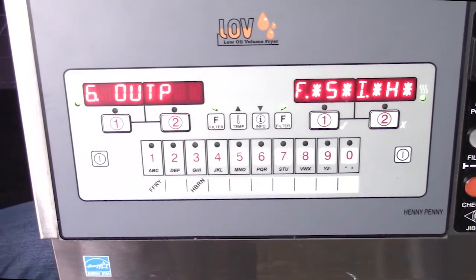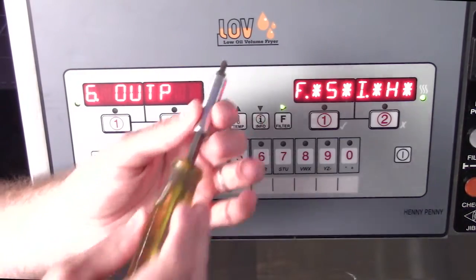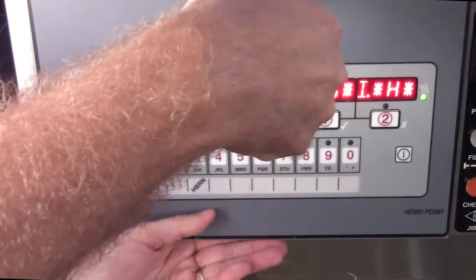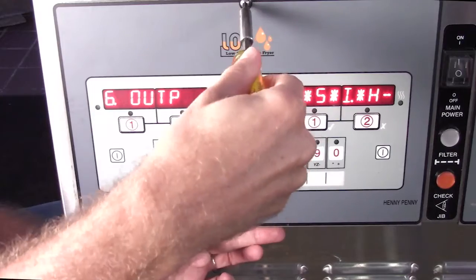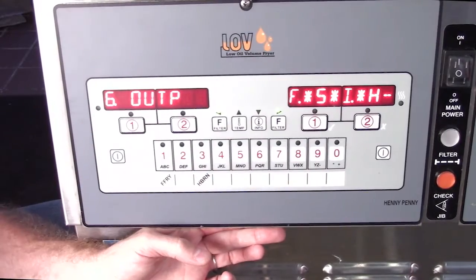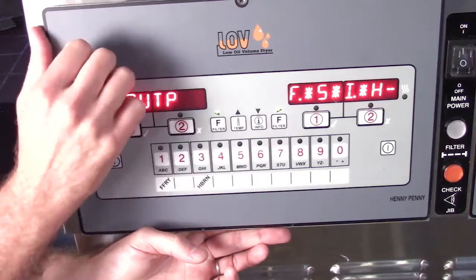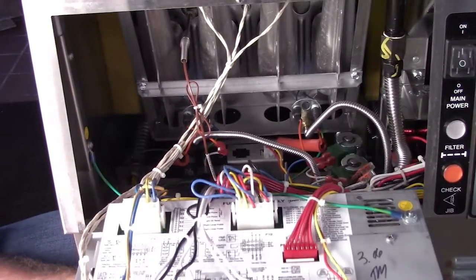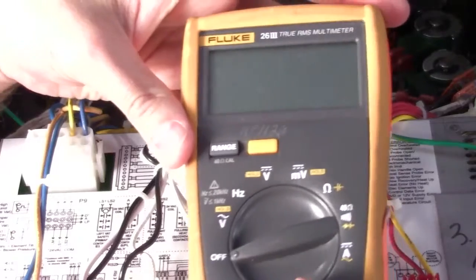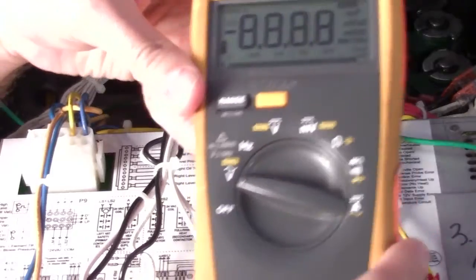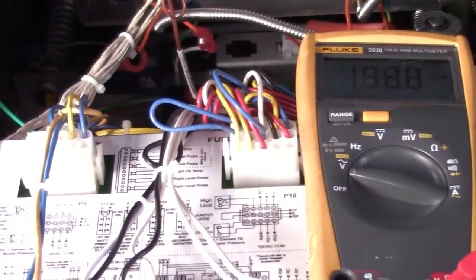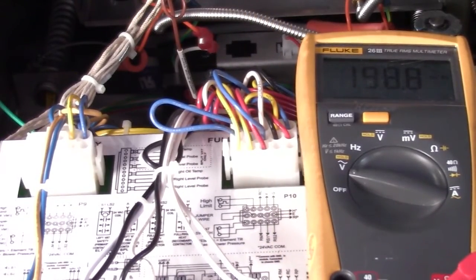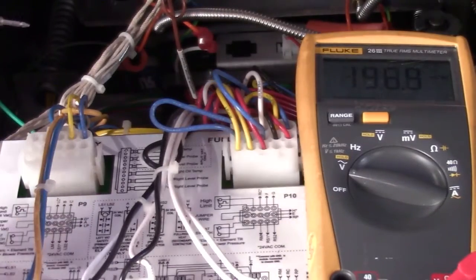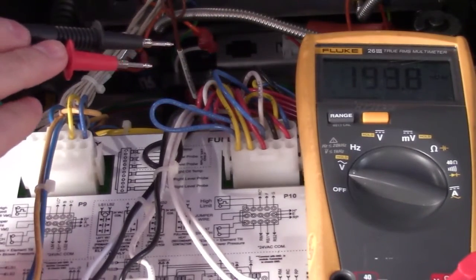We want to go ahead and check our voltages, so what I'm going to need to do then is I'll go ahead and grab my Phillips screwdriver. I'm going to loosen this, backing that off a little bit. Dropping this down, pushing up here on the bottom to support it, and then I can hinge it so it's going to hook onto it. We're going to set it to AC voltage. But where I need to check my voltages then to make sure I'm getting my 24, 25 volts going out to my gas valve.